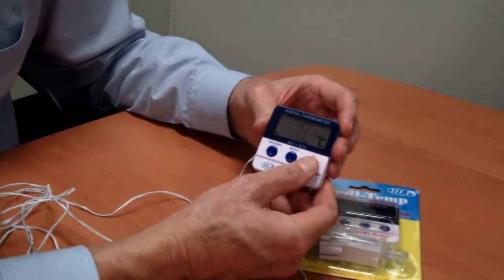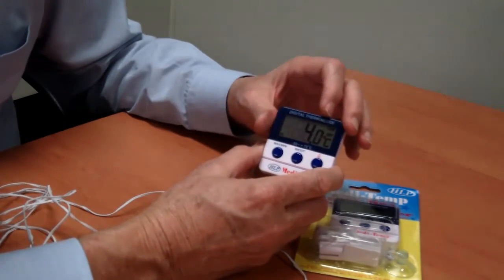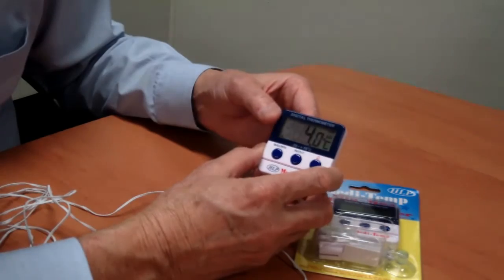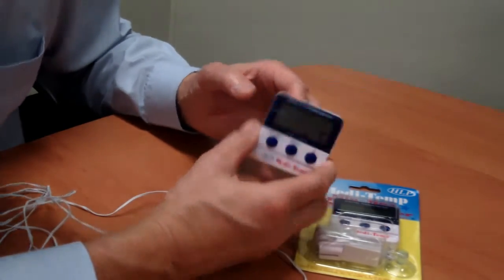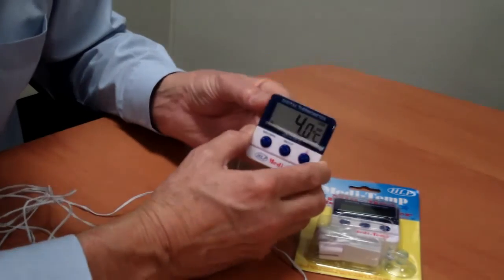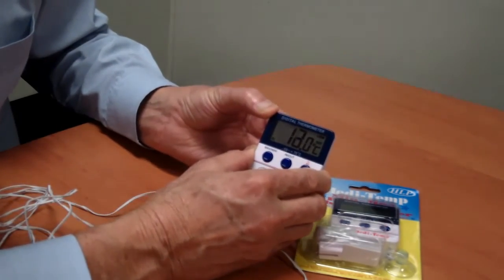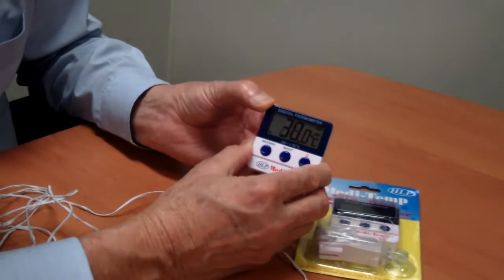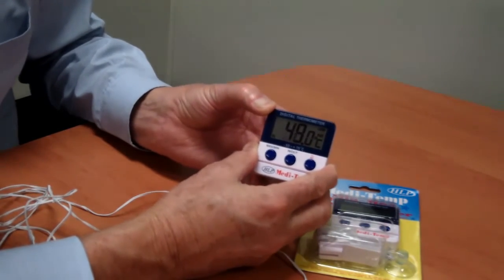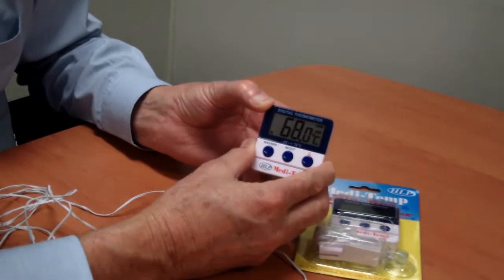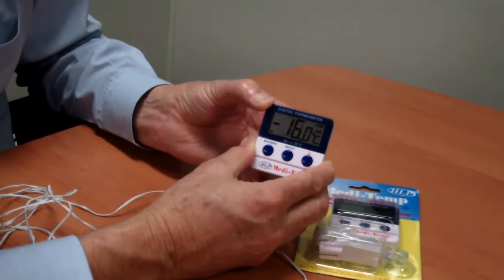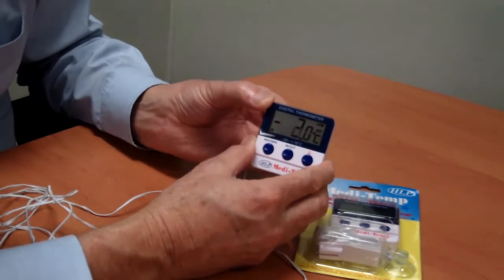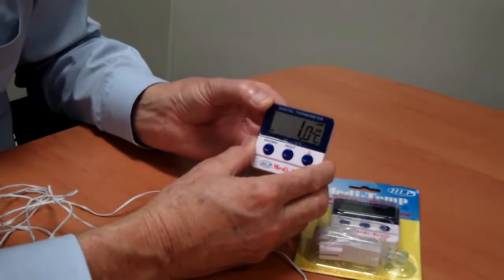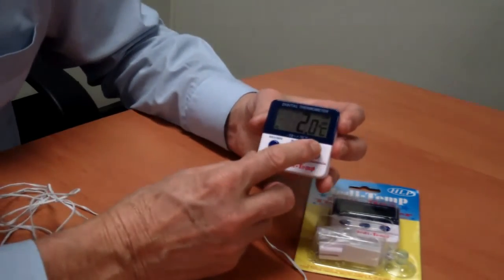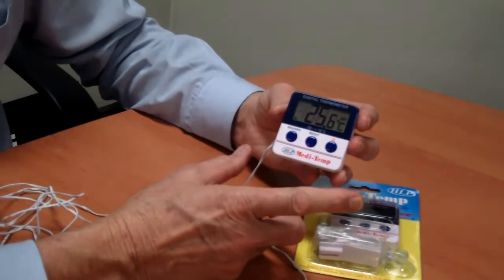If I push the alarm symbol again, it's wanting the low temperature. So that's set at 4 degrees, but I want the low temperature for my vaccine fridge to be 2 degrees, sorry. So I'll just push and hold that button, and again let it cycle through. It only takes a few seconds, going right through its range. That's 70 degrees, and it goes back to minus 50, minus 30, minus 20, minus 10, 8, and I want to make this 2 degrees, so I'd set that at 2. Push the alarm again, and that's it.